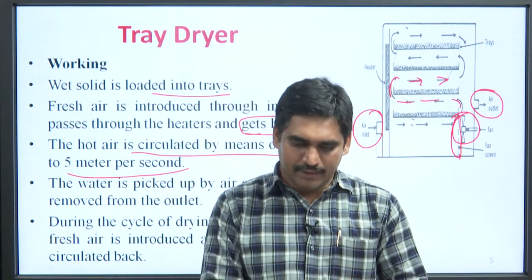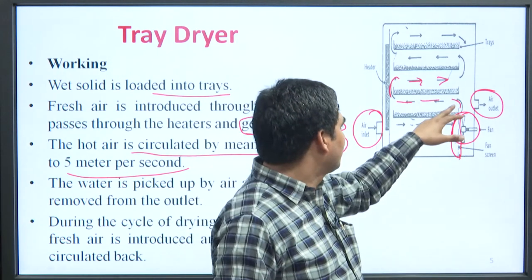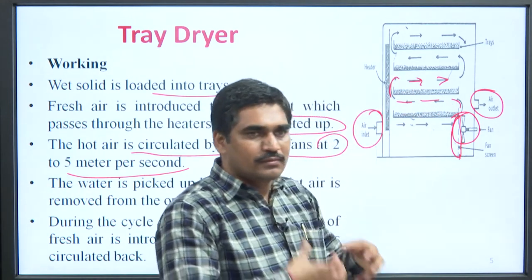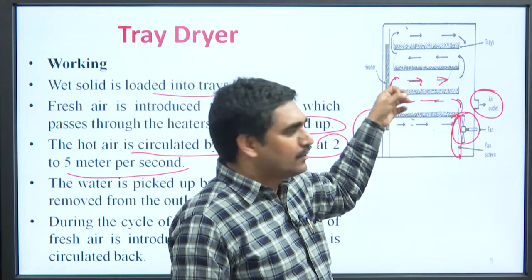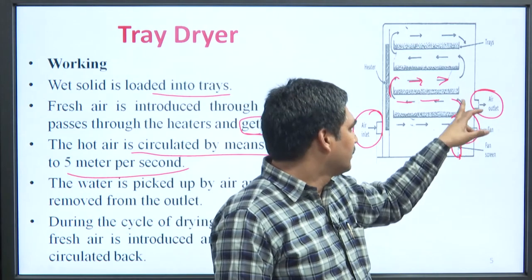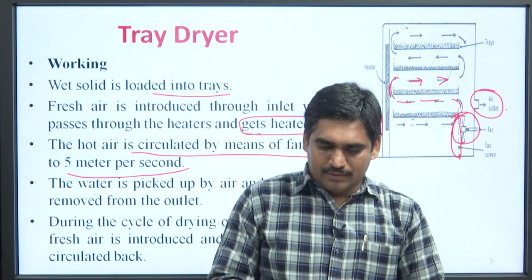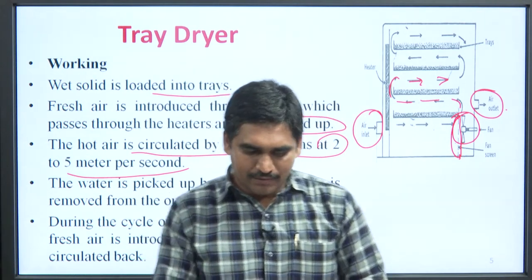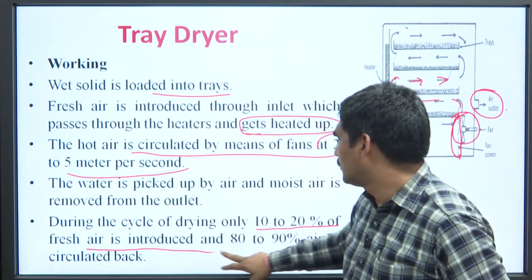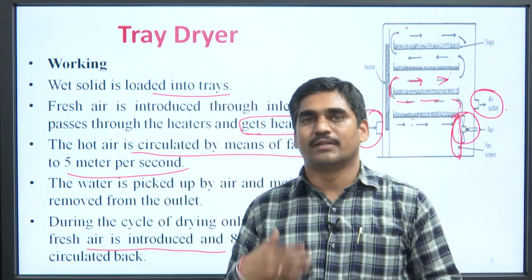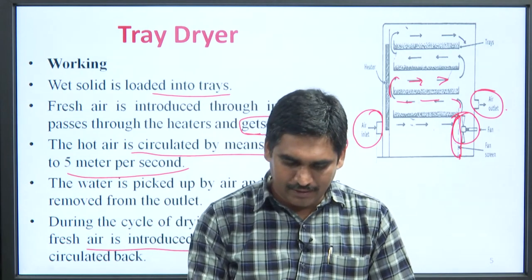Water is picked up by the air, and moist air is removed from the outlet. From the surface of the wet material, water is removed by the hot air, and the moisture is removed through the air outlet. During the drying cycle, only 10 to 20 percent of fresh air is introduced, and 80 to 90 percent of the air is circulated back.